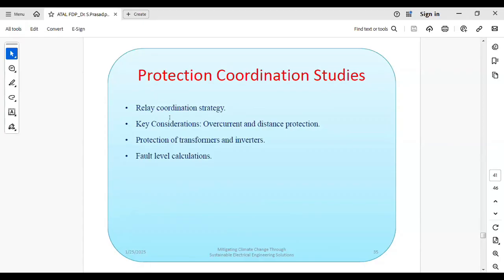When there is a fault, at what point it has happened and which part of the network has to be disconnected, for smooth operation of the rest of the system. It is not that the major part of the network will get disturbed due to a fault at one point. So an engineer has to look into how to coordinate the protecting devices in a PV plant when it is connected to the grid. Okay, so that is nothing but the protection coordination studies.